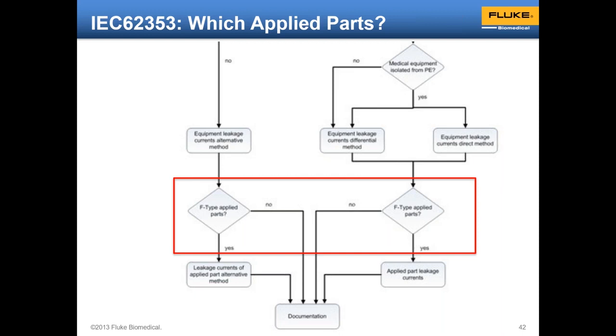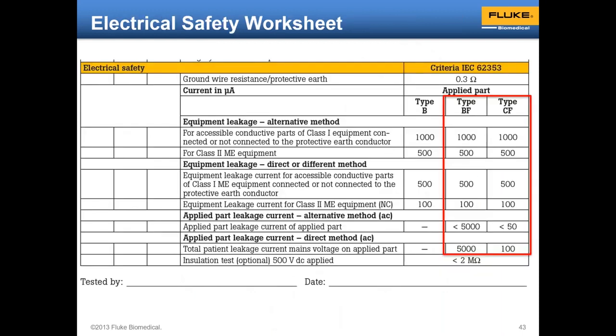Just so you can see how that bottom part of the decision tree works, and documenting the results. In this case, we would do that in the worksheet. So let's have a little closer look at what that part of the worksheet includes. Applied parts under IEC 62353 need to be tested for F-type applied parts, that is BF or CF. These are isolated from ground, all right? The B-type applied parts, like temperature sensors, are referenced to ground.